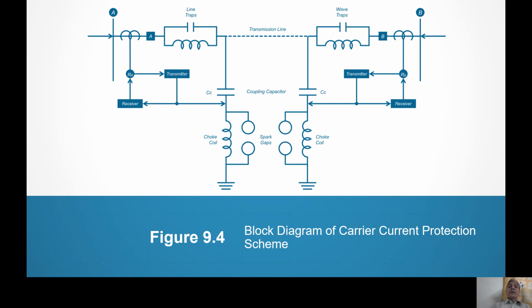Now, the function of the coupling capacitor: Xc is equal to 1 upon 2 pi Fc. So it allows only high frequency signals to pass through, because Xc is very low. In the transmission line, power frequency signal is passing 500 megawatt, 200 megawatt, 300 megawatt. That does not come down to the coupling capacitor, because the coupling capacitor will show very high impedance and will oppose it, and will not allow the power frequency signal to come down. Only the carrier frequency signal, the high frequency signal, will go to the transmission line. So in the transmission line, both signals get mixed, power frequency and carrier frequency.